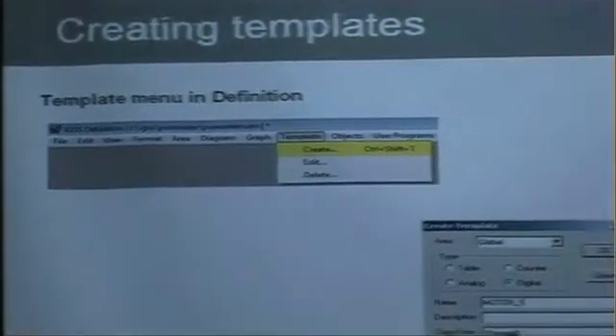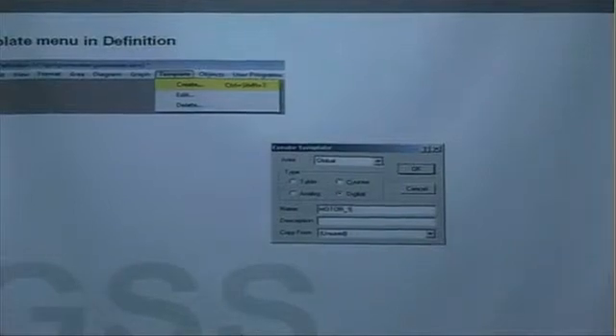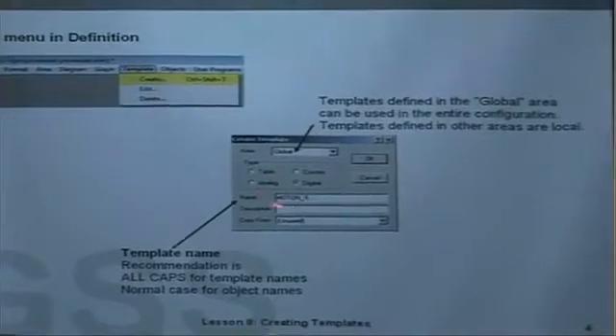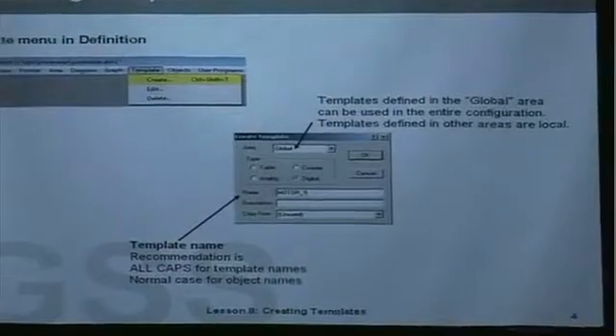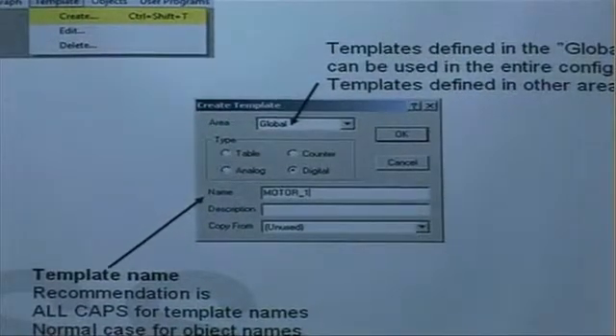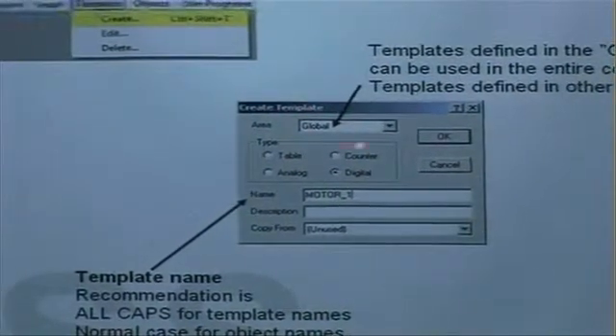When you want to create a template you go into the definition module. You go into the template menu and click create. You come into a dialog box where you can choose between the four object types I just mentioned. You give the template a name — as you can see I've written MOTOR_ONE in all caps. This is our recommendation: all caps for template names and normal case for object names. I have also specified the global area so I can use this template in the whole configuration.